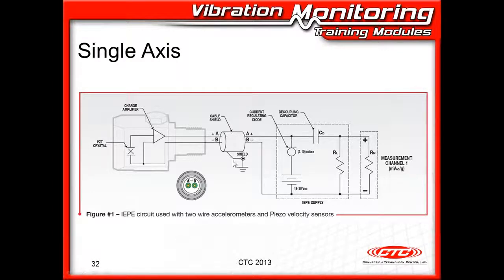Here's your single axis sensor. You can see the shield drain wire here being taken to earth ground. This IEPE power supply that's denoted here by the 18 to 30 volt DC battery, the diode, and the coupling capacitor, that's built into your data collectors and your condition monitoring systems today. So you have these already built in, and you're just going to use this power supply to not only power the sensor, but to also measure the vibration. And that coupling capacitor decouples the DC bias voltage, so only the AC vibration is measured by your data collector.